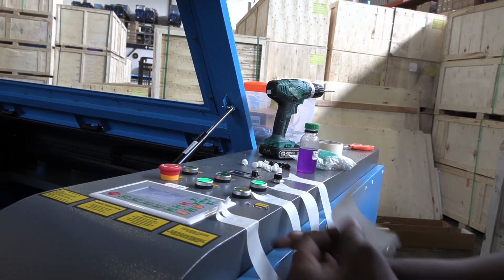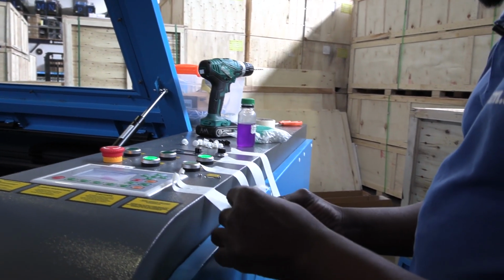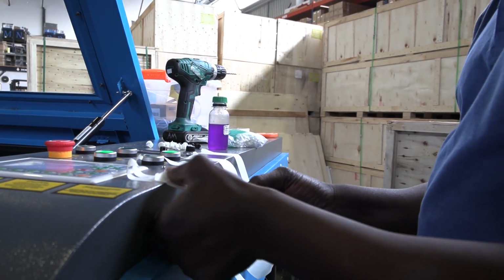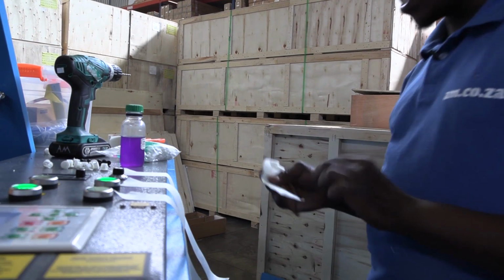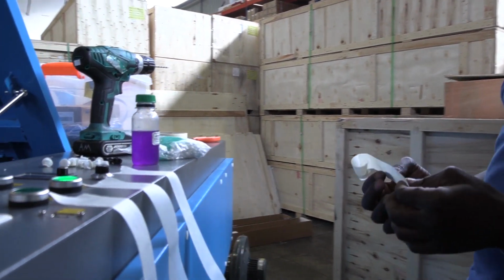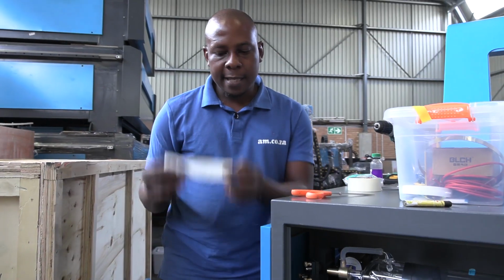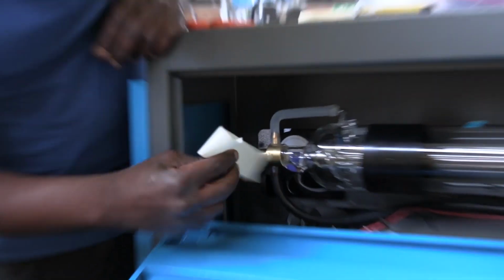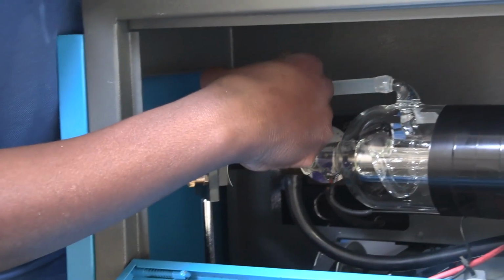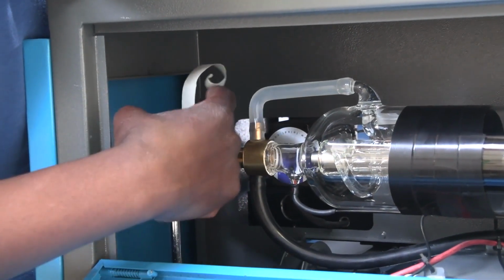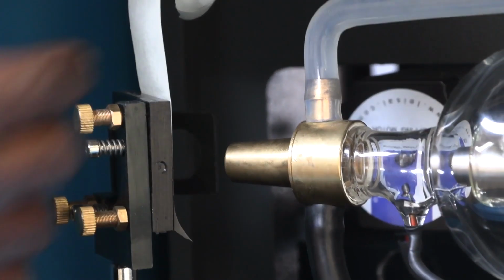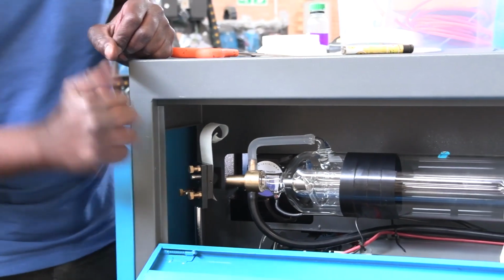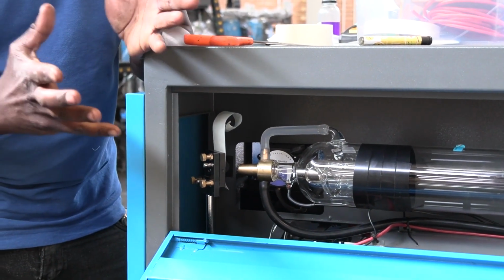Just going to cut this one in half and tape them over each other, just to give the masking tape a little bit of resistance when bending it and marking with the laser. Right, so what I want to do is stick this on the first mirror right about there, so that when I pulse straight from the tube, I can check if it's within the circle of the mirror. It doesn't have to be centered, but just within the circle of the mirror.